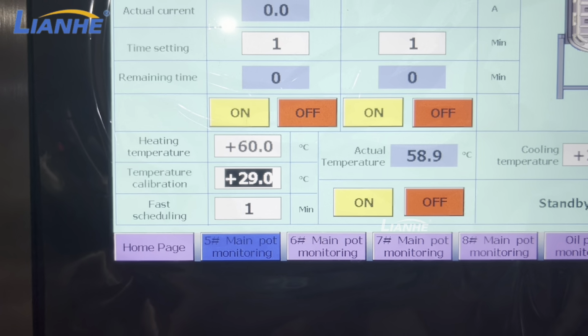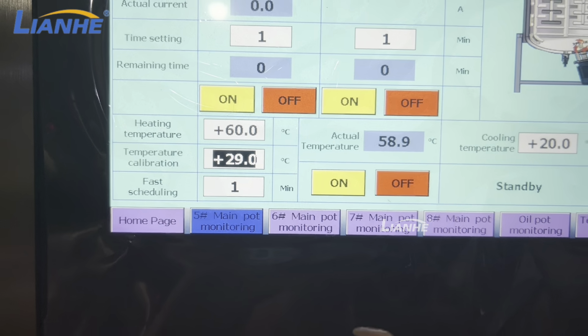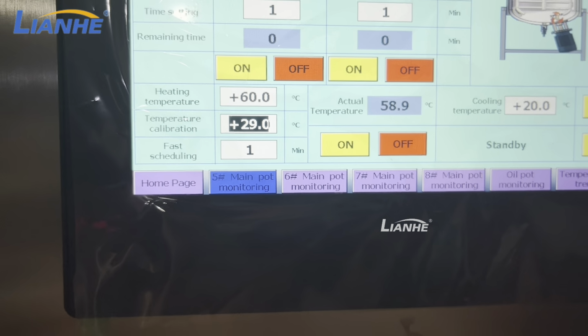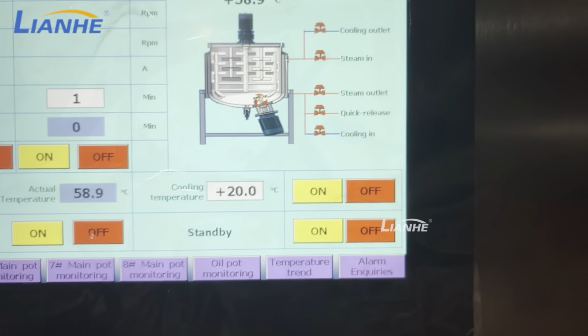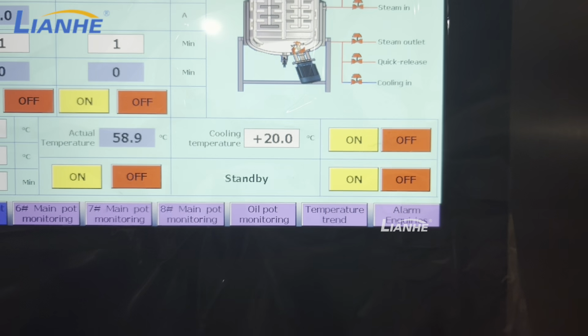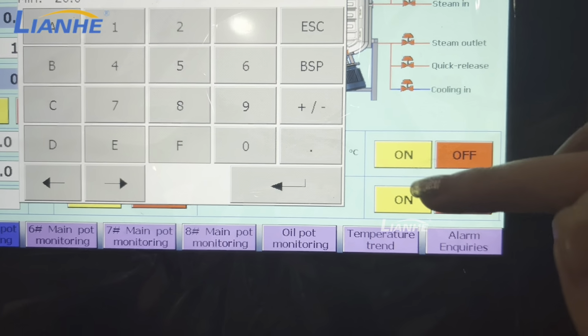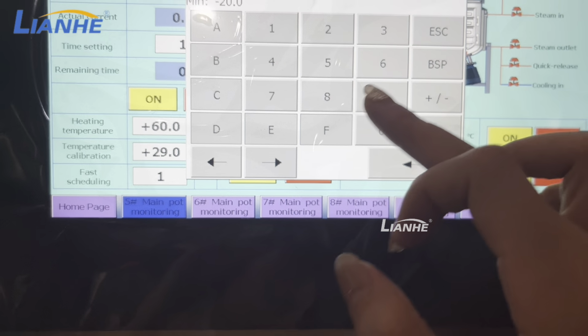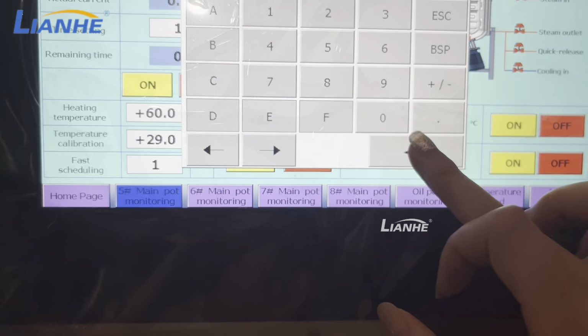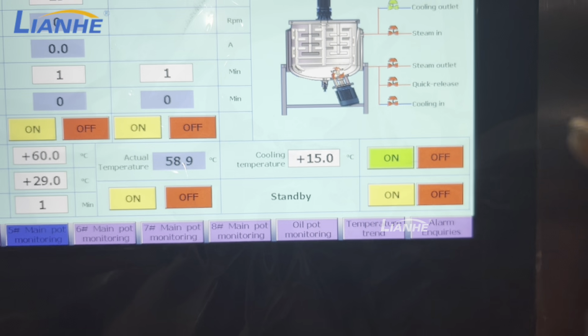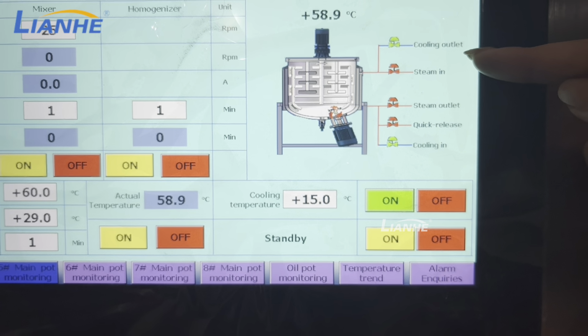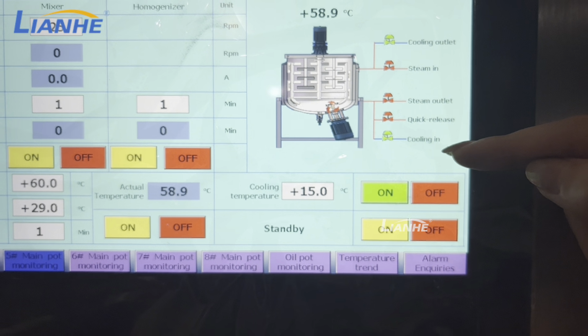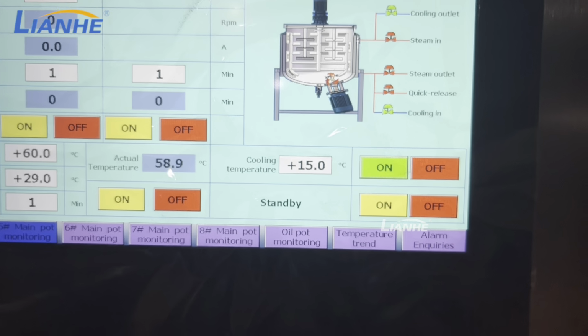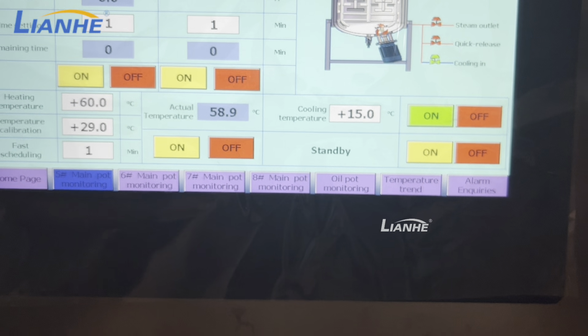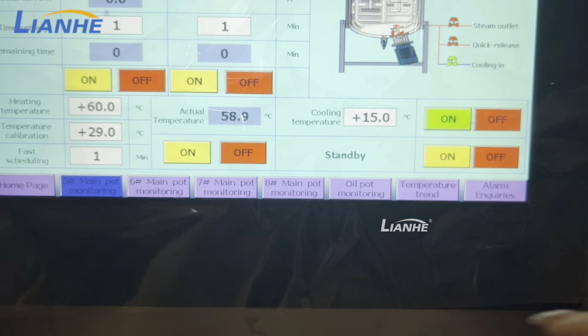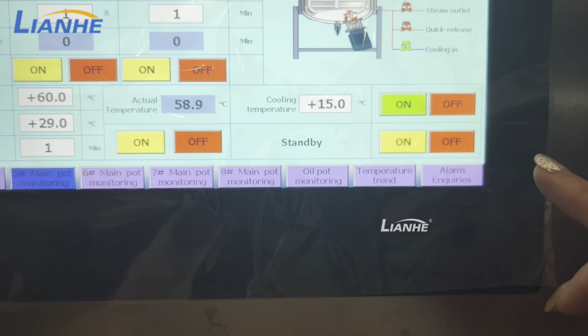29. And now the actual temperature is very close to the temperature you need. And here is the cooling function. Here you can set the temperature you need to cool down to, for example, 15, and turn on. You can check the cooling water outlet and cooling water in valve is open. That means when the temperature arrives at what you set here, the cooling function will stop automatically. Okay, now turn off.